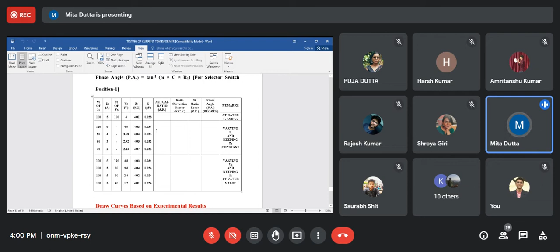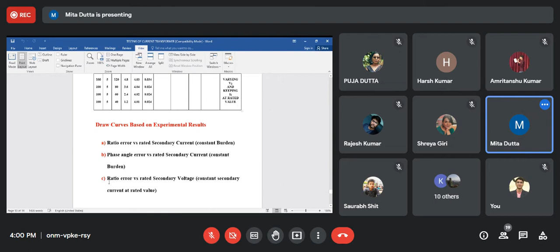Based on this formula, and after finding out the phase angle and ratio error, you are going to plot curves: ratio error versus rated secondary current, phase angle error versus rated secondary current, ratio error versus rated secondary voltage, and phase angle error versus rated secondary voltage.